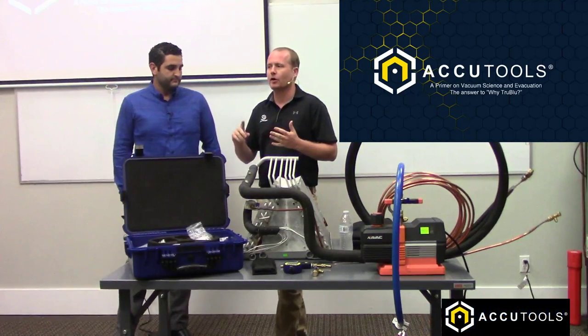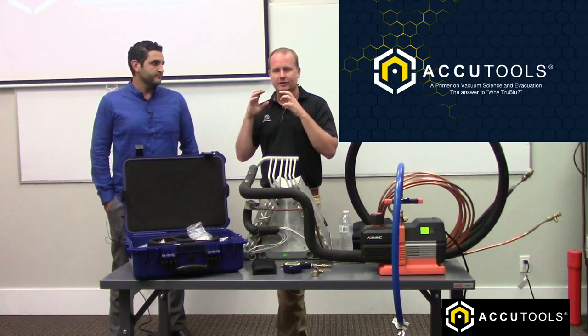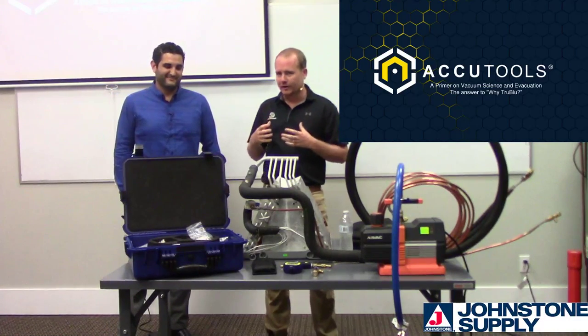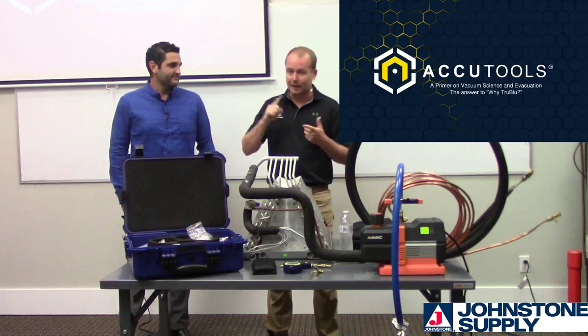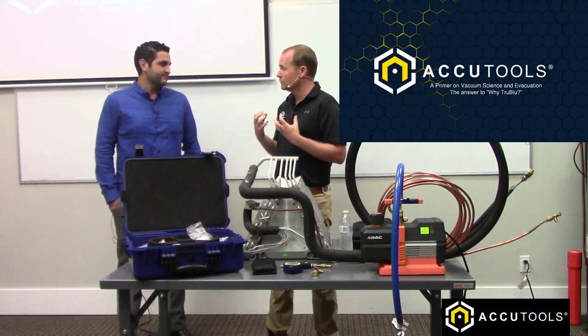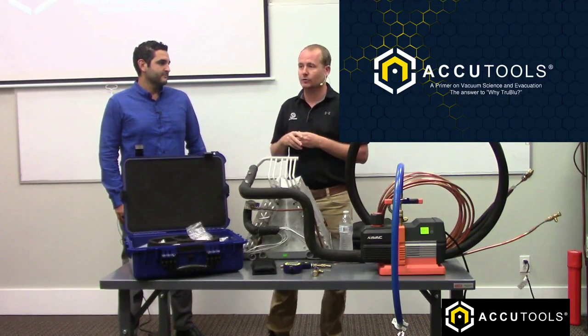It's important to note right off the top: there's always going to be a cohort of technicians who think what I'm about to talk about is overkill. But what they don't realize is that a lot has changed in our industry over the last few years. We've got POE oil, which is probably the biggest factor. POE oil is highly hygroscopic, which means it absorbs moisture, and when it absorbs moisture it changes into an acid via hydrolysis.